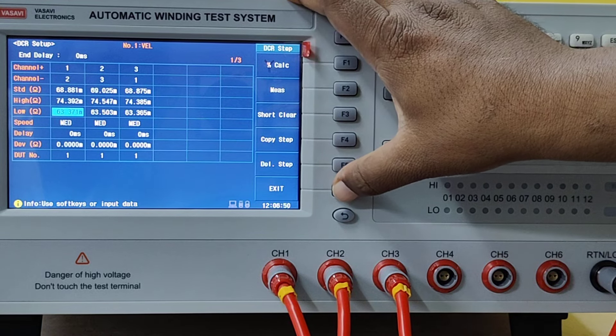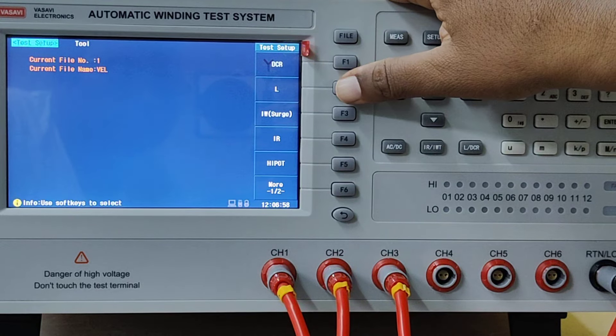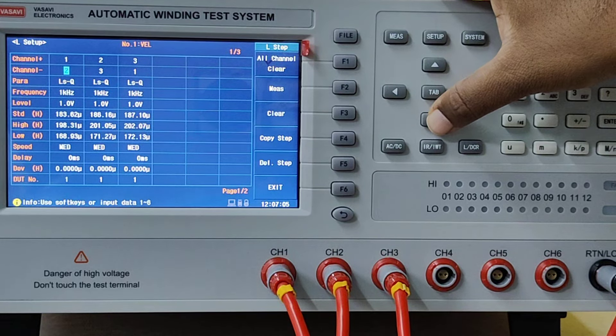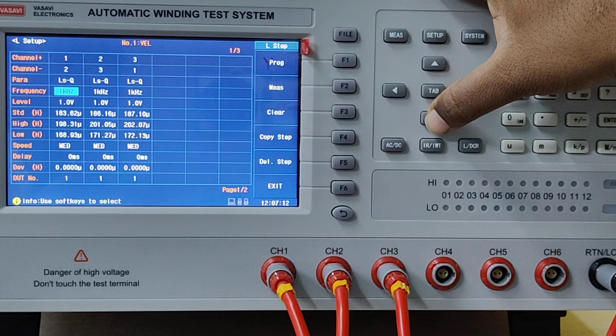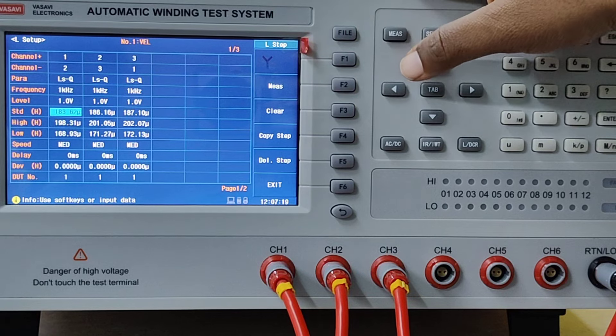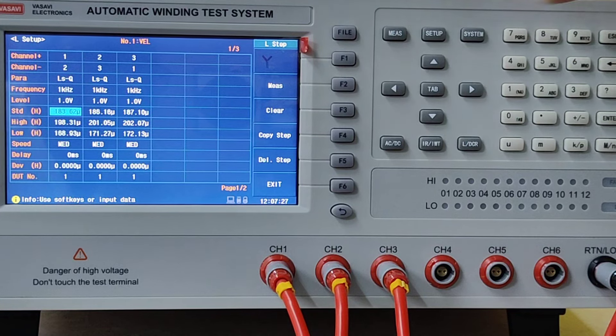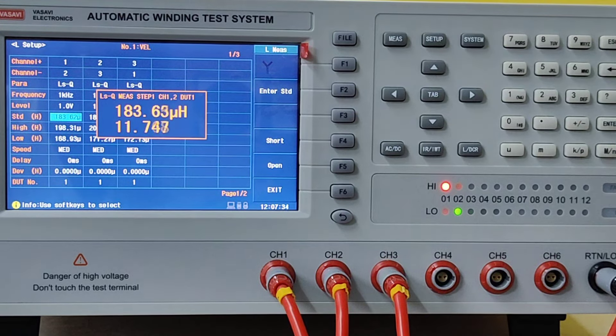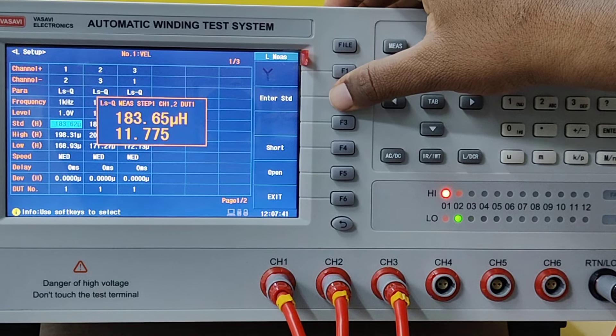Once those parameters are fed, go to the second parameter: inductance. In inductance, it is done the same way — channel 1, channel 2, inductance and Q. For this value, frequency setting is 1 kHz, test voltage 1 volt. This is the standard value. You can punch the values using the keypad, or when the standard is connected, you simply press Measure. You get the measured values of inductance and Q. Simply press Enter STD — STD stands for Standard.